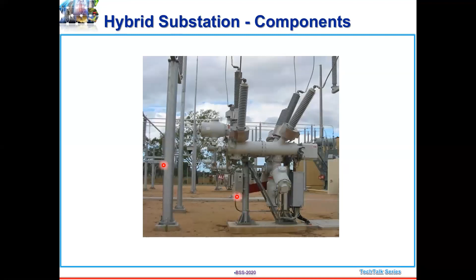So this is basically PASS, and what happens is, this is the CT portion, the outdoor CT, where you have the whole thing, CT, CVT, PT, breaker, isolator, everything in this one unit. So this is where you have the CT, and then you have the PT here in this portion. You have one PT here and another PT here on the incoming portion. This is the bus PT, and you have the circuit breaker in this portion. This is the circuit breaker. Isolator. This is the first bus isolator. Then you have the circuit breaker here. Okay, this is how the whole system has been made very compact.